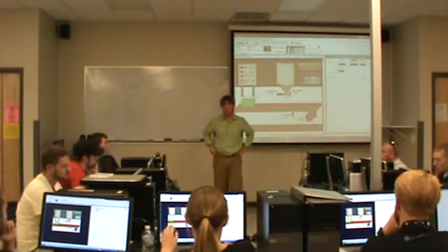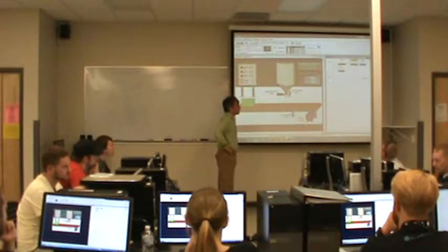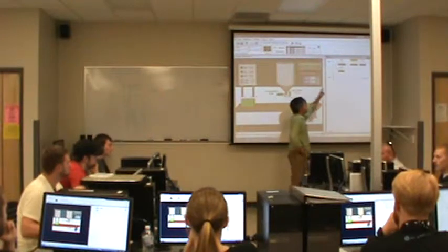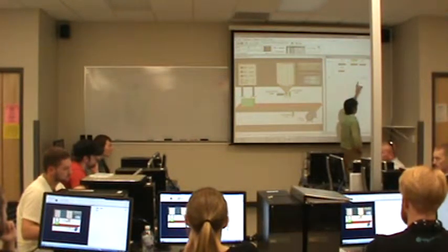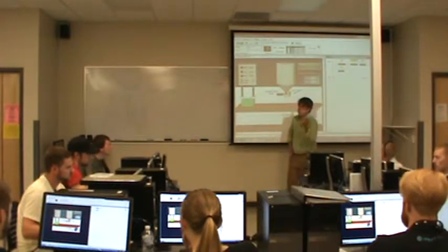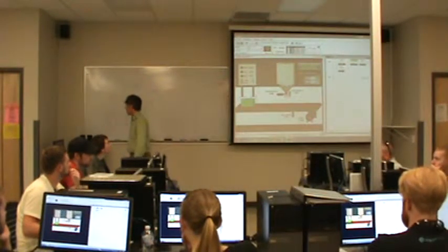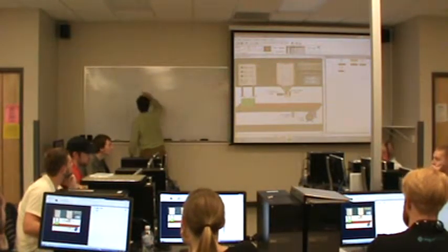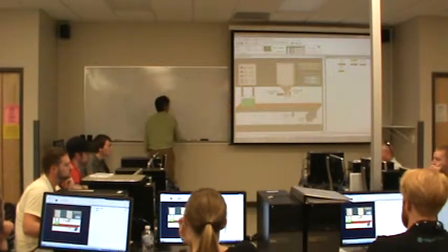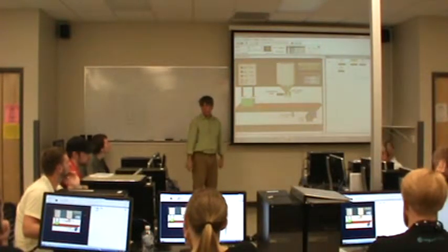And we're not going to use memory bits much yet. We'll use them in a minute once we find, or probably next class, once we find the truth table programming will be a little bit inadequate. Okay, so you understand what happens, right? You press the start button, the stop button being normally closed allows power to pass, run lamp comes on, run lamp seals itself in, and away we go. We hit the stop button, it breaks the seal-in and turns off the lamp. Okay, so standard seal-in. I don't have to deal with truth table programming for the start and stop button. Basically now I have a lamp address on output 2/2, which I can reference to decide whether or not the system is running.